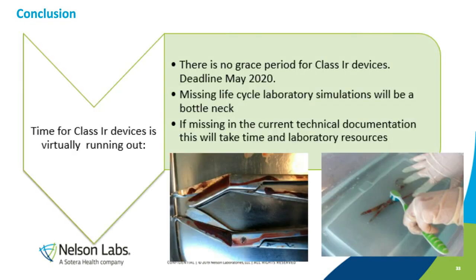What I really want to conclude on is that the time for Class 1R devices is virtually running out. Like I said before, there's going to be no grace period for Class 1R devices, and the current deadline is May 2020. Missing lifecycle laboratory simulations will be a bottleneck. So we want to make sure that if there's any type of validation work that needs to be performed, it is done now versus at the end of 2019. If missing in the current technical documentation, this will take time and laboratory resources.